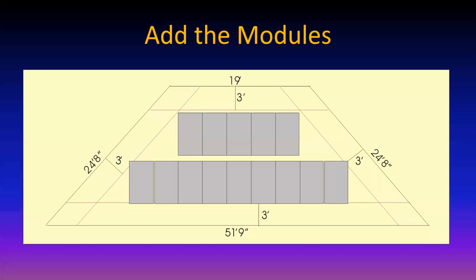If you can put them all in zone 1, then it's less expensive to mount them on a rack. But right now, because the modules are so cheap, it's worth it to spend a little extra money on racking and let them slip into zone 3 and 2, as long as you maintain your fire access, as was mentioned earlier. So this is just a simple design here where we got 5 and what do we got, 9 there? 1, 2, 3, 4, 5, 6, 7, 8, 9, 14 modules, all pretty much in zone 1. And what can we do with those 14 modules?